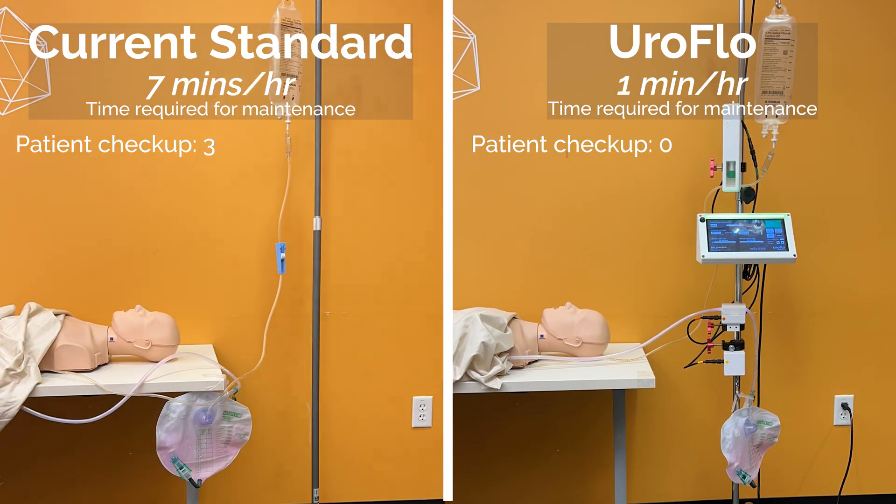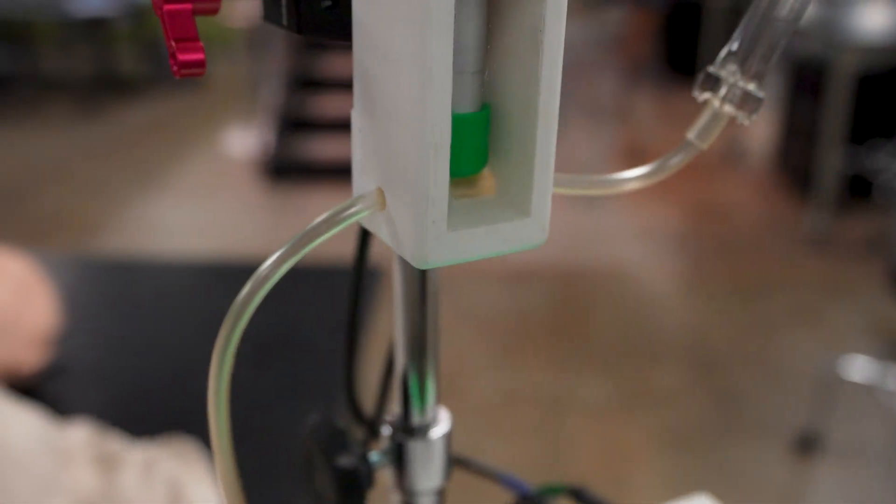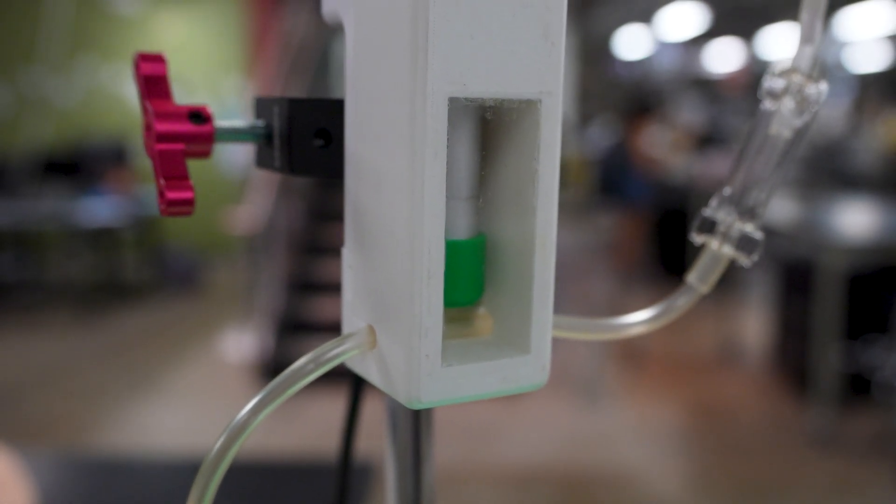In effect, UroFlo autonomously optimizes continuous bladder irrigation flow. In practice, our device modulates the saline flow by means of a tube compression apparatus. This component externally squeezes CBI tubing to increase or decrease saline flow.